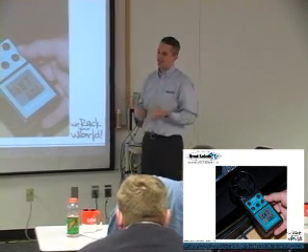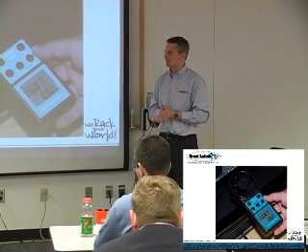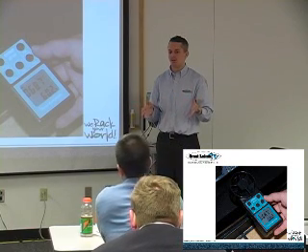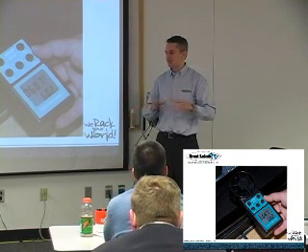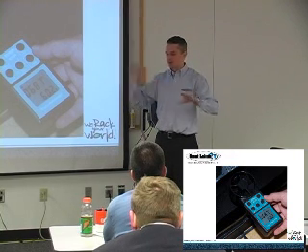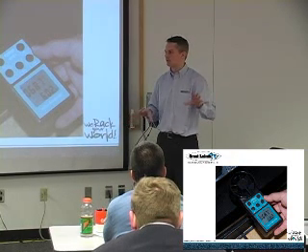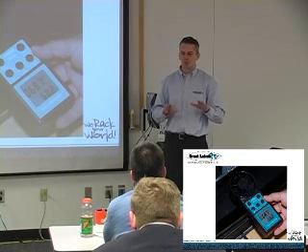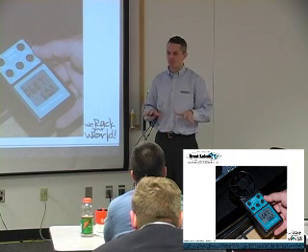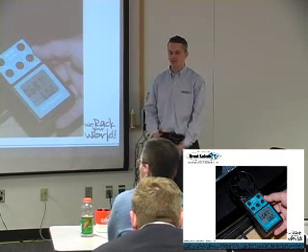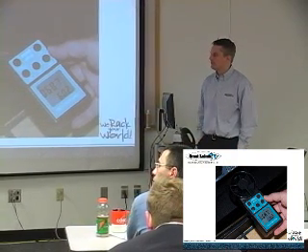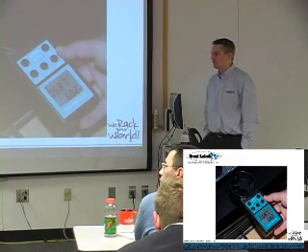It's the one thing that when we go in and try to reevaluate efficiencies for facilities, if we see that scenario, we usually recommend migrating. You don't need all your blades in one spot. It would be nice in a perfect world. But if you can balance that out with lower CFM equipment, you can really improve a lot of efficiency. You see 30 to 40% improvement just by reducing the amount of CRAC you need to force air to that one monster cabinet with all the blades in it. So the load balancing works incredibly well.